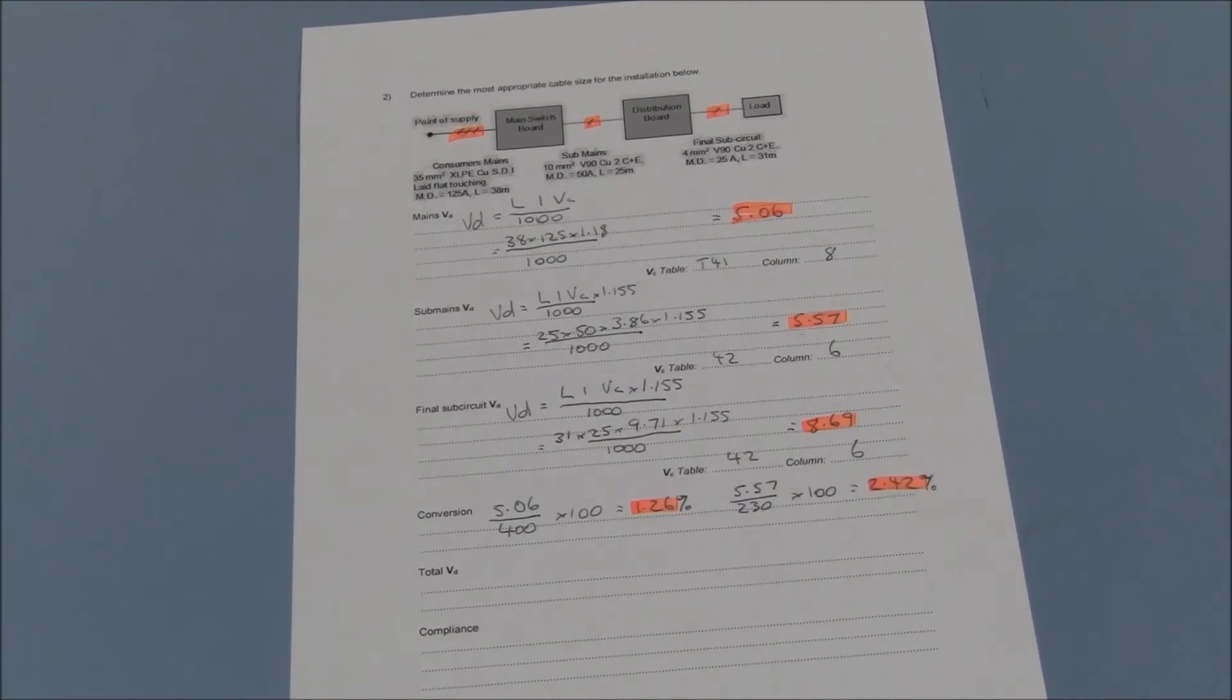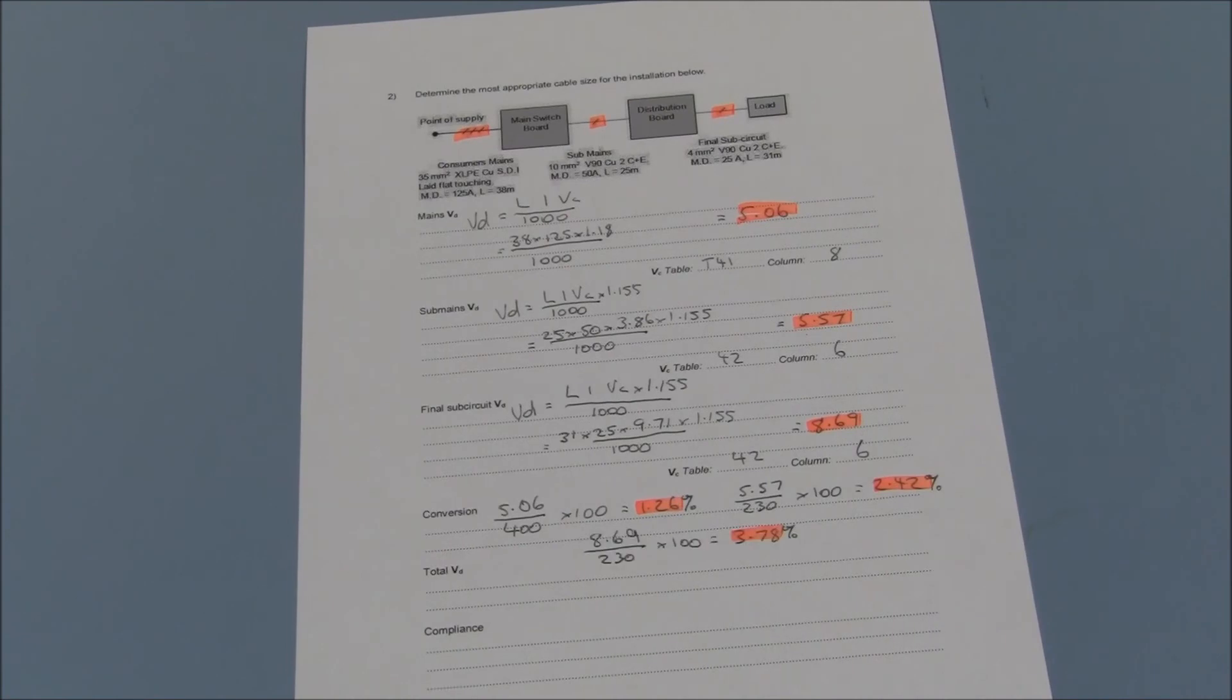The sub main attracted a voltage drop of 5.57 volts, which is 2.42% of the supply voltage of 230 volts. The final sub circuit attracted a voltage drop of 8.69 volts, which is 3.78% of the supply voltage.